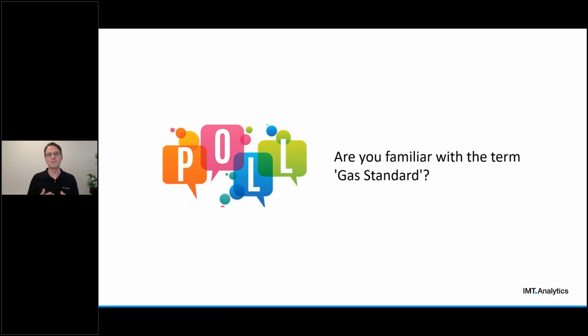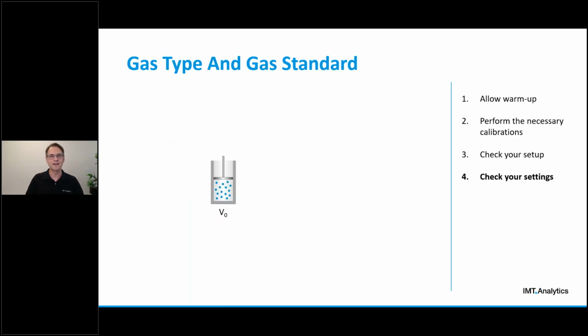And now let's bring that value to 100%, as the gas standard is one of the most, if not the most important setting on your gas flow analyzer. So let's jump in here. So the question is, why do we need to set a gas type and gas standard on our gas flow analyzer?